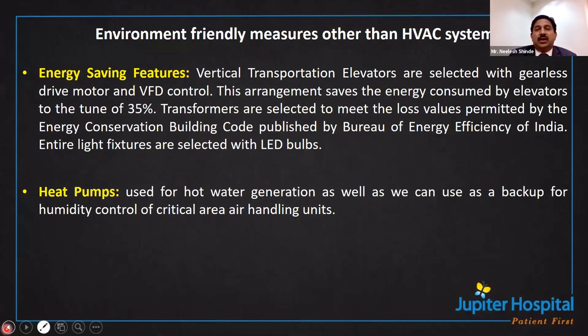But what we have done in our hospital is that when we are taking patients, maybe 12 hours, we can maintain that. But after the working hours, when there is no patient, there is no heat generation from the machine. So at that time, you can increase the temperature. There is absolutely no issue at all. If you check the original technical data sheet of any make, they will always write up to 30 degrees, no issue at all. Relative humidity is also up to 85 to 95% non-condensing. So that will never have any impact. It will go wrong only if the temperature goes beyond that.